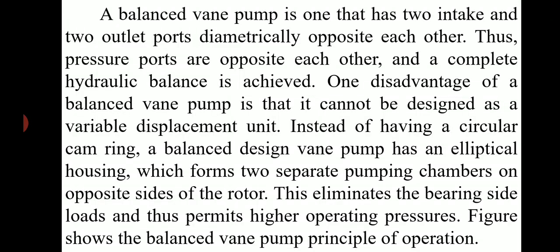A balanced vane pump is one that has two intake and two outlet ports diametrically opposite each other. Thus, pressure ports are opposite each other and a complete hydraulic balance is achieved. One disadvantage of a balanced vane pump is that it cannot be designed as a variable displacement unit.